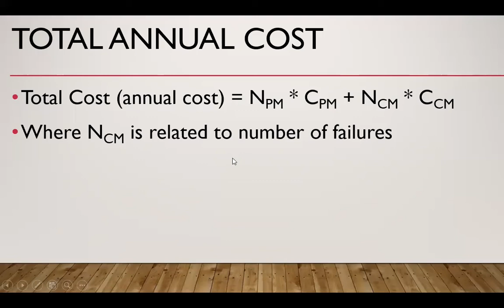So for example, if we have a total of 15 machines, question is what will be the total cost if preventive maintenance is done every 3 months? And cost of preventive maintenance given is 650, and cost of reactive maintenance or corrective maintenance is 5,500. This is the probability of failure 1 month after maintenance is probability 0.1. 2 months after maintenance, the probability is 0.2. 3 months after maintenance, the probability is 0.3, and so on. And the total probability is equal to 1.